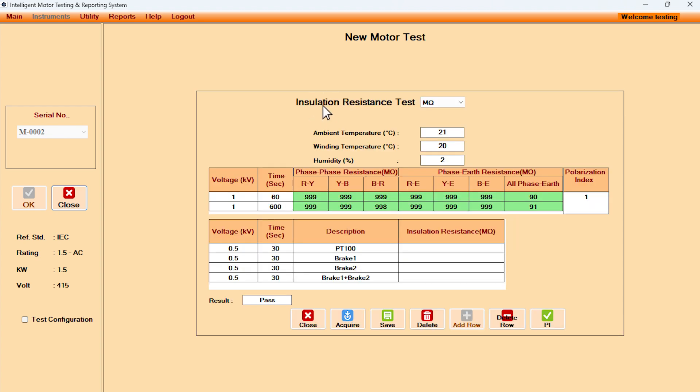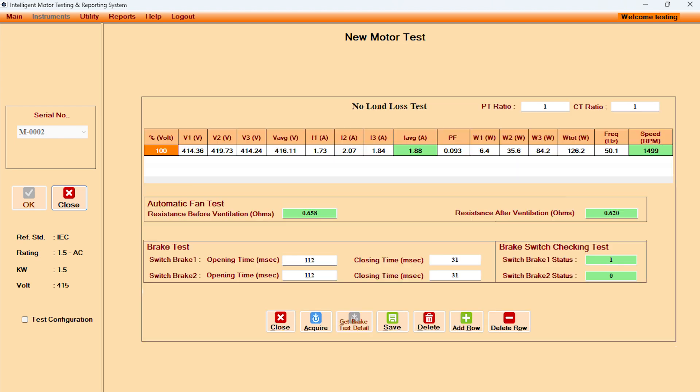In insulation resistance test, it displays applied voltage and the duration. Measured insulation resistance gets populated with a click on the acquire button. Polarization index is also displayed instantly. There is a facility to measure the insulation resistance of various accessories for special motors.